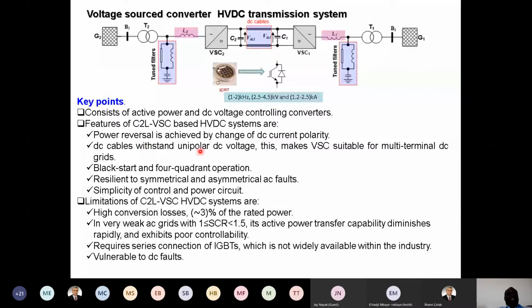And here is the basic structure of two-terminal VSC HVDC transmission systems. In this, at least one of the converters must control active power, and the other one must control DC voltage directly or indirectly. But this is the basic thing, so you have to define a DC voltage directly. The converter that controls active power varies the current up and down at a constant voltage defined by the controller controlling VDC. In that way, we control the active power and so on.